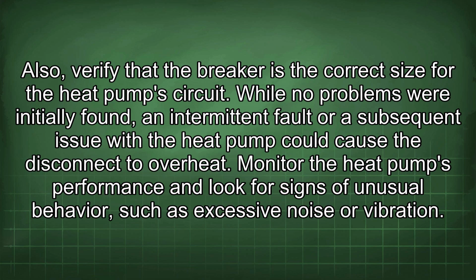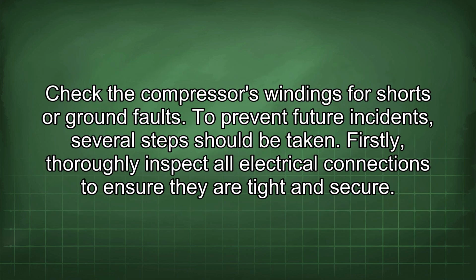While no problems were initially found, an intermittent fault or subsequent issue with the heat pump could cause the disconnect to overheat. Monitor the heat pump's performance and look for signs of unusual behavior, such as excessive noise or vibration. Check the compressor's windings for shorts or ground faults.